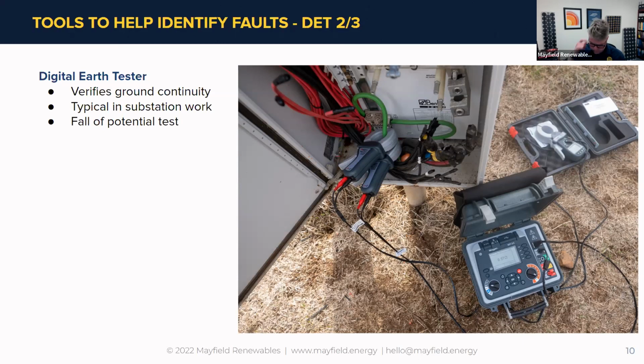In the picture here, we actually have two different pieces of equipment. On the top right, over on the far side, is that clamp-on earth tester I talked about earlier, where we got various readings on both sides of those module connectors, and it was a very quick way to see what had a continuity ground and what didn't. That's a split clamp that puts a pulse out and returns it through earth and the attachment elements of the array and back to earth. So a clamp-on earth tester is a great device to quickly go through the string and find out what has good grounds and what doesn't.